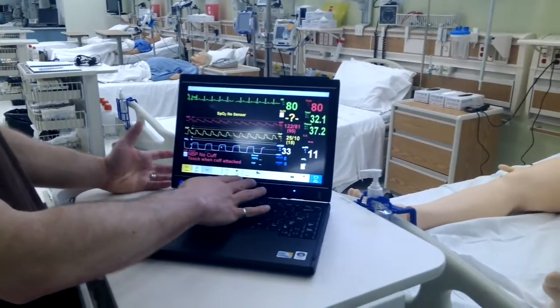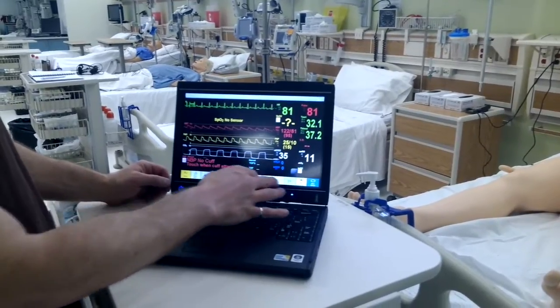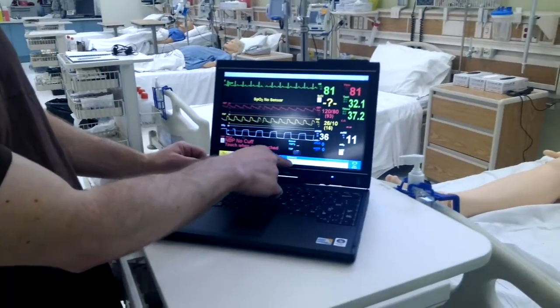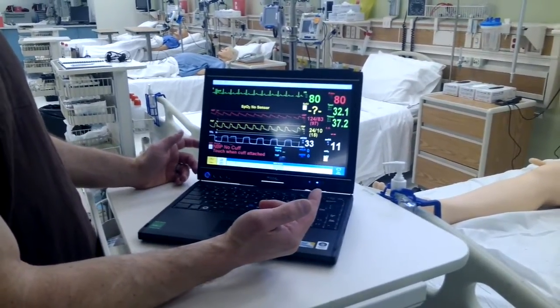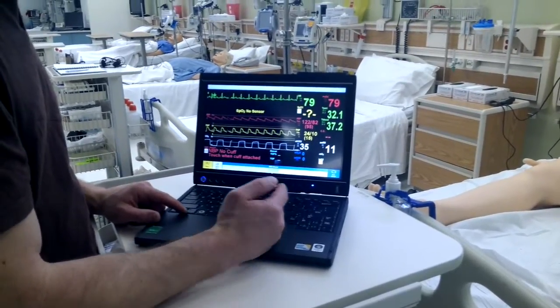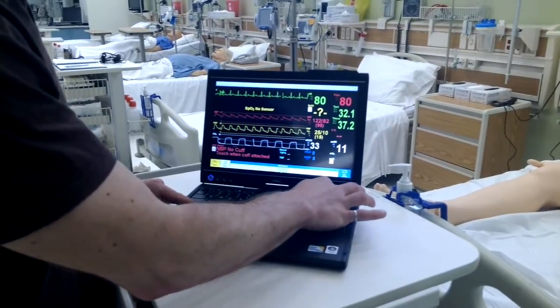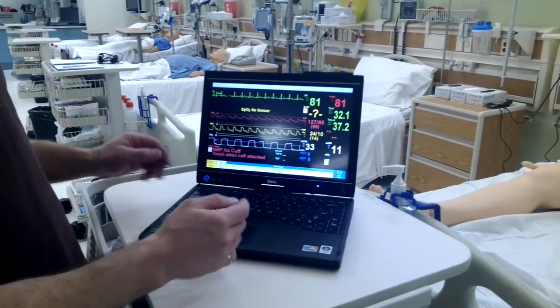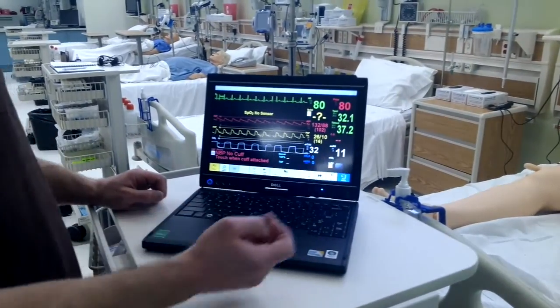On the patient monitor you have different options. If we click these arrows, we can set our QRS volume. The laptop volume is obviously very low here, so we're not hearing it right now — maybe it's muted. This is how you would set the QRS volume, and we can go back to the main screen.